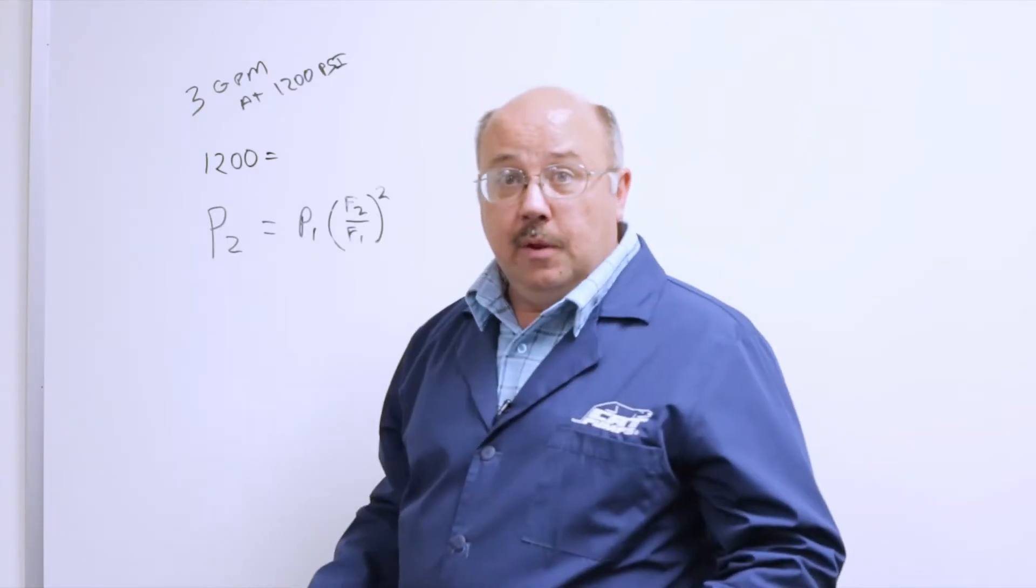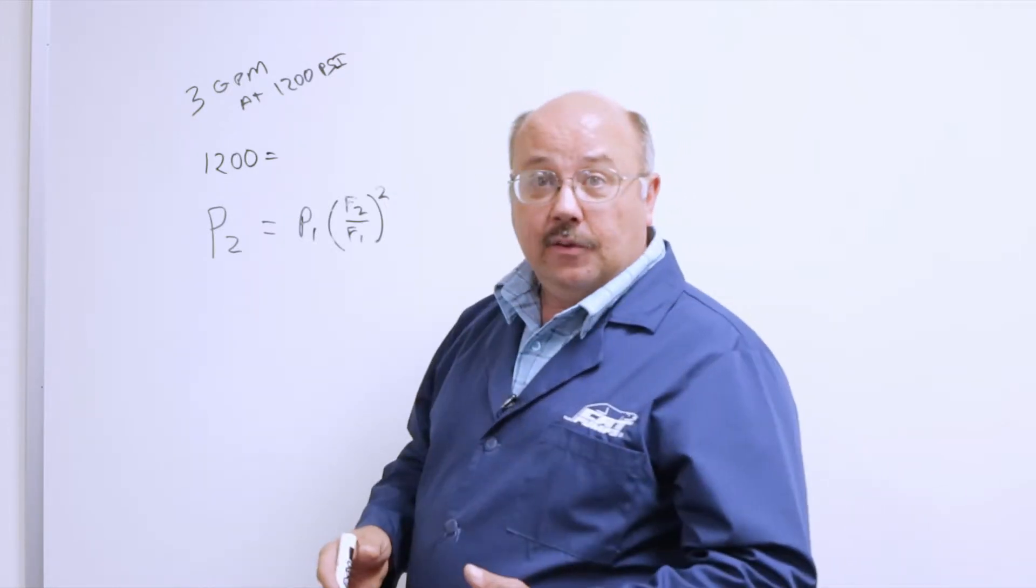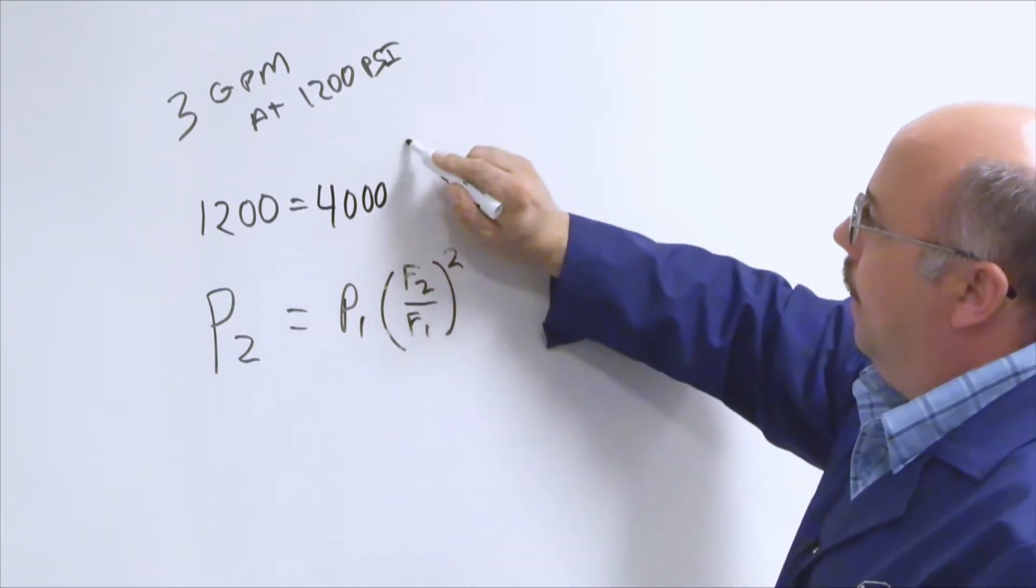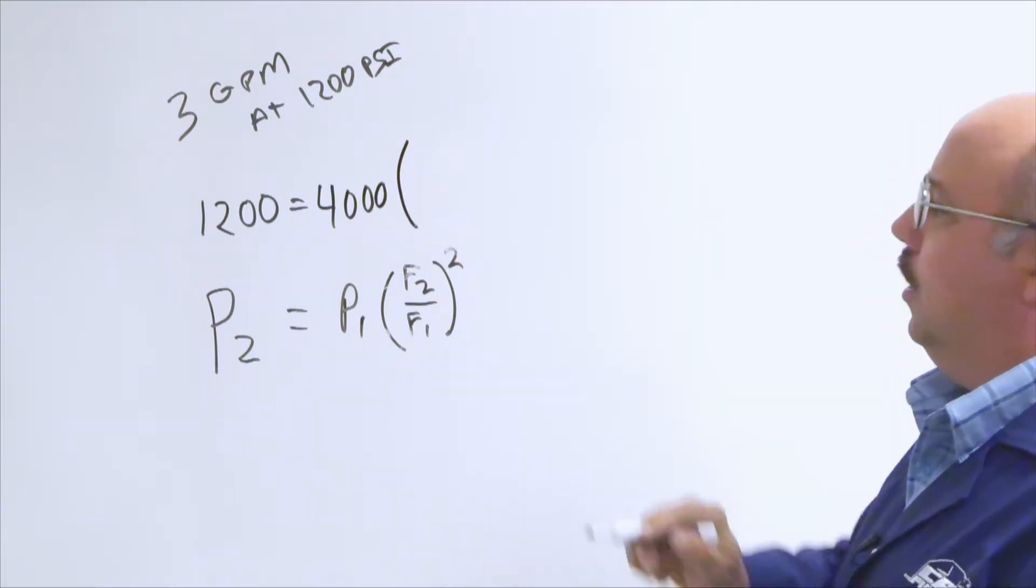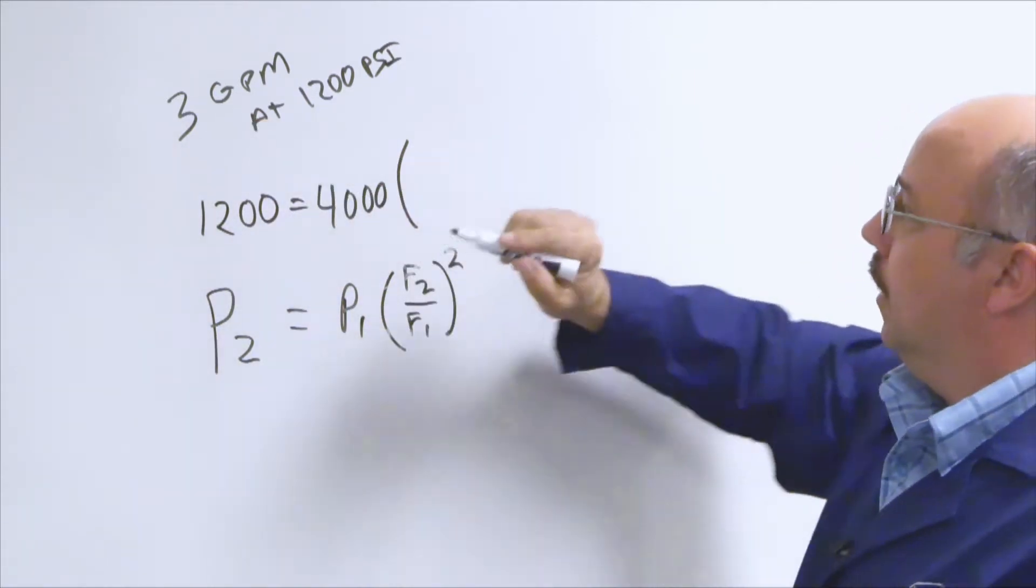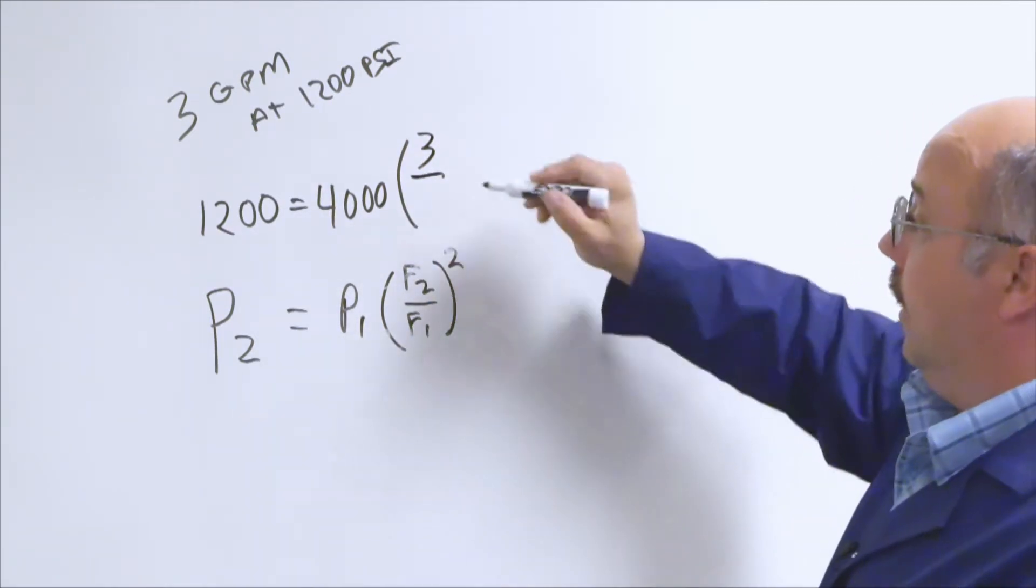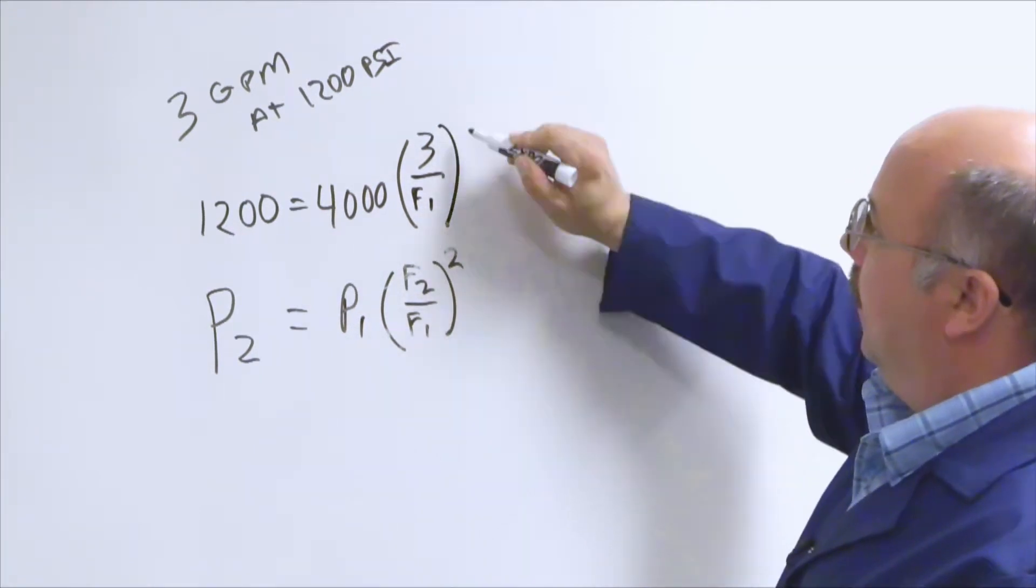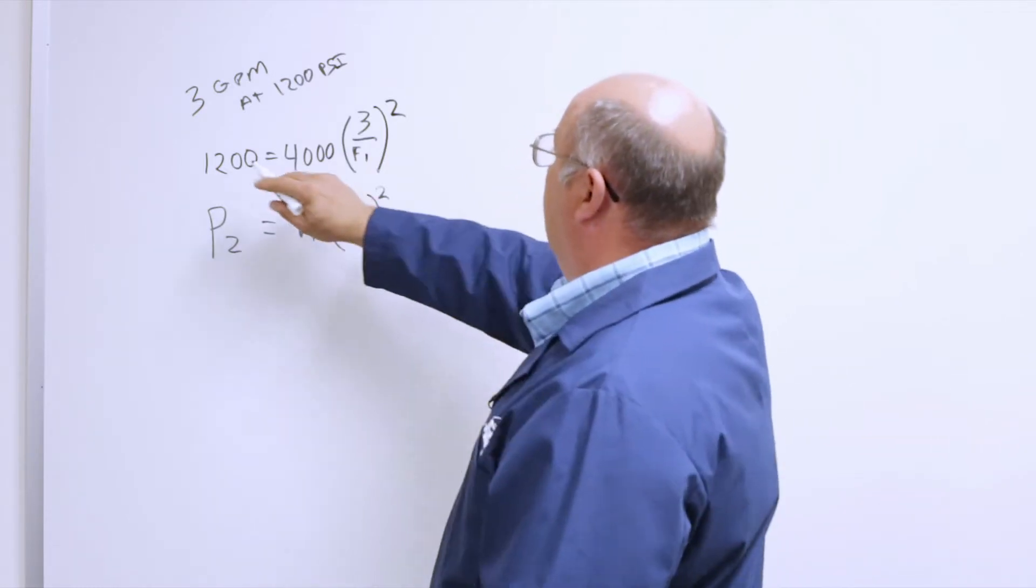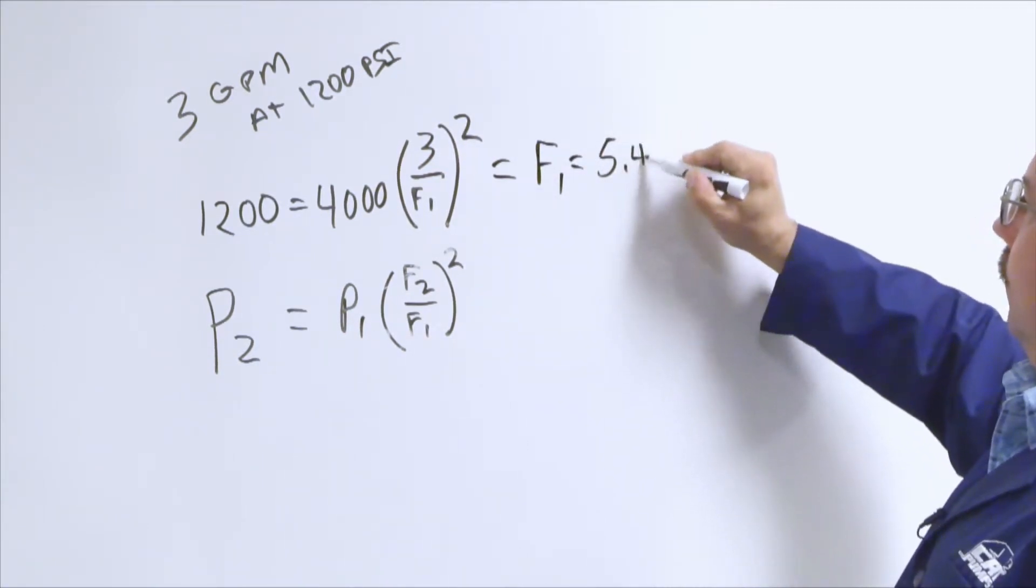So for this, P2 we're going to use is 1,200 because that's the pressure we want to end up with. So what do we use for P1? We're going to use the relationship that we know. We're going to put 4,000 here. Now, what goes for F2 and F1? Do we know what the flow is that relates to the 1,200 psi? Yes, we're going to run at 3. Do we know what flow relates at 4,000? No, we don't know that right now. So we're going to continue to call that F1, and then we're going to square this.